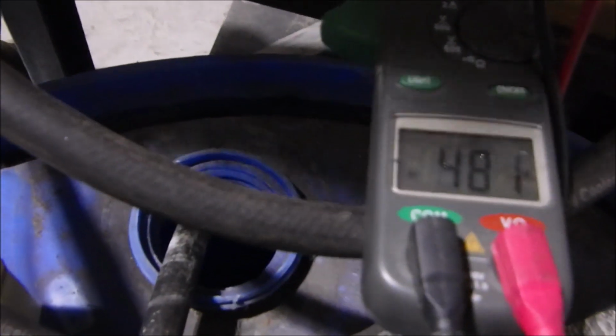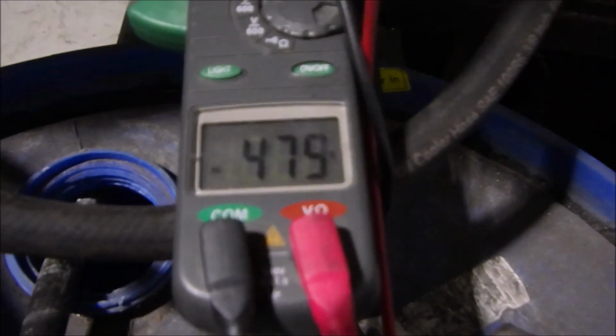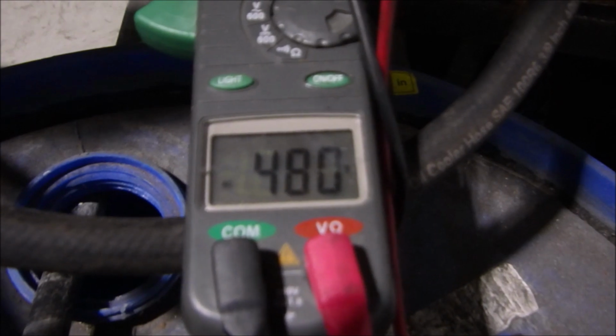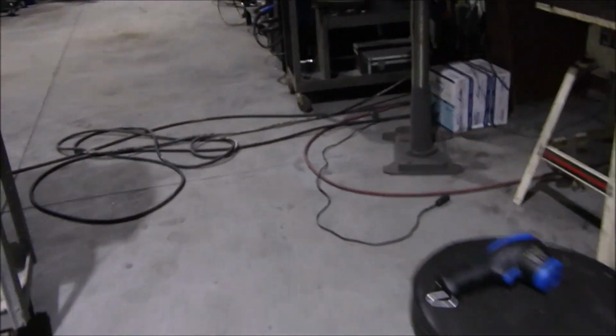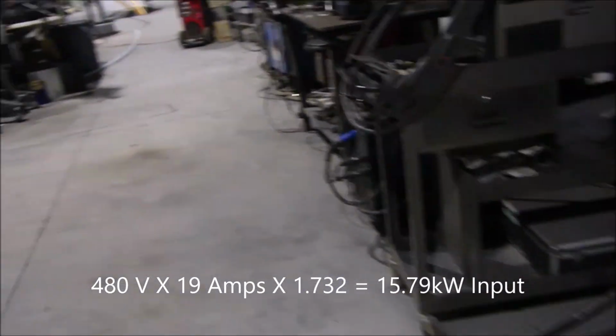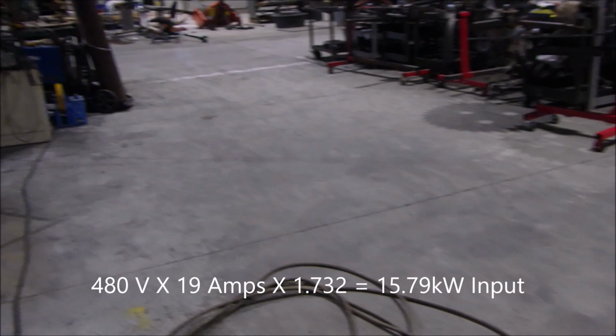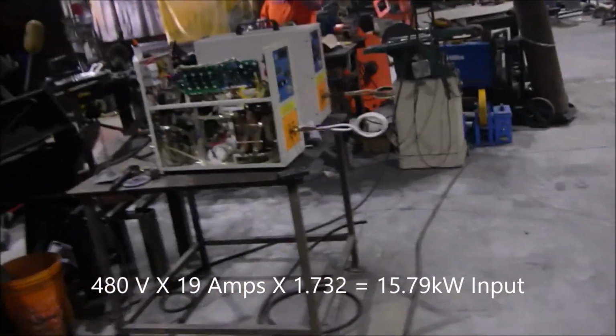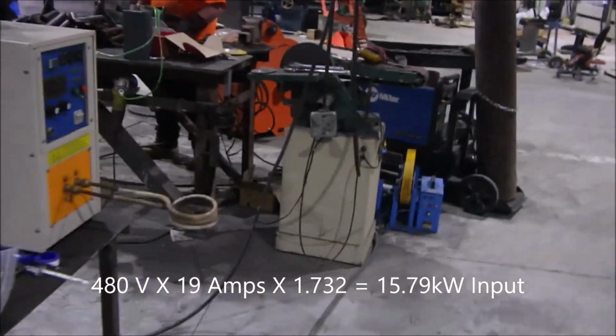Let's kill it and measure the voltage on the three-phase back here. Now it says AC. Well, what do you know, 480 volts. So if you take 480 times, being generous, 19, and multiply by 1.73, the square root of 3, you get a number less than 25,000.